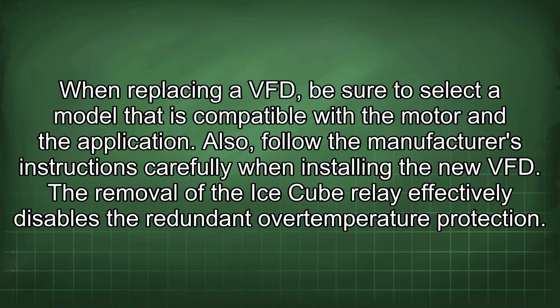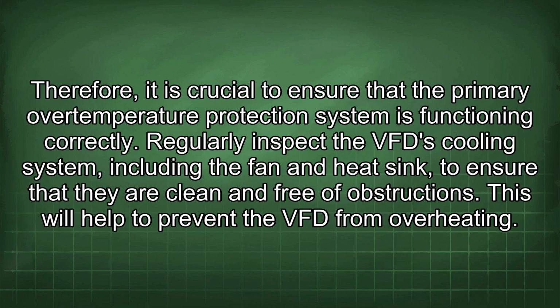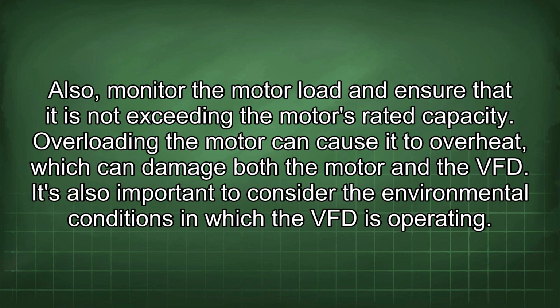The removal of the ice cube relay effectively disables the redundant overtemperature protection. Therefore, it is crucial to ensure that the primary overtemperature protection system is functioning correctly. Regularly inspect the VFD cooling system, including the fan and heat sink, to ensure that they are clean and free of obstructions. This will help to prevent the VFD from overheating. Also, monitor the motor load and ensure that it is not exceeding the motor's rated capacity. Overloading the motor can cause it to overheat, which can damage both the motor and the VFD.